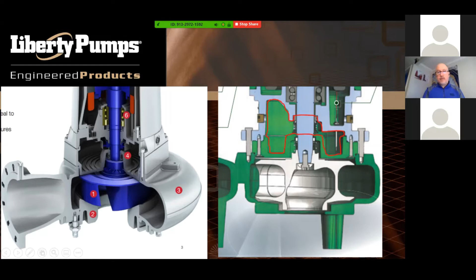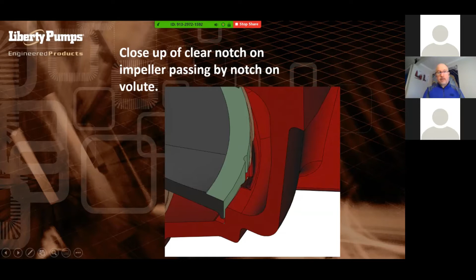And then another shot of another manufacturer here. Here's a little better picture and a close-up of the clear notch as it's passing the notch on the volute. So this is a groove cut into the impeller here, and then you've got this kind of ramp or groove cut into the volute area. So that's what we're calling clear notch.